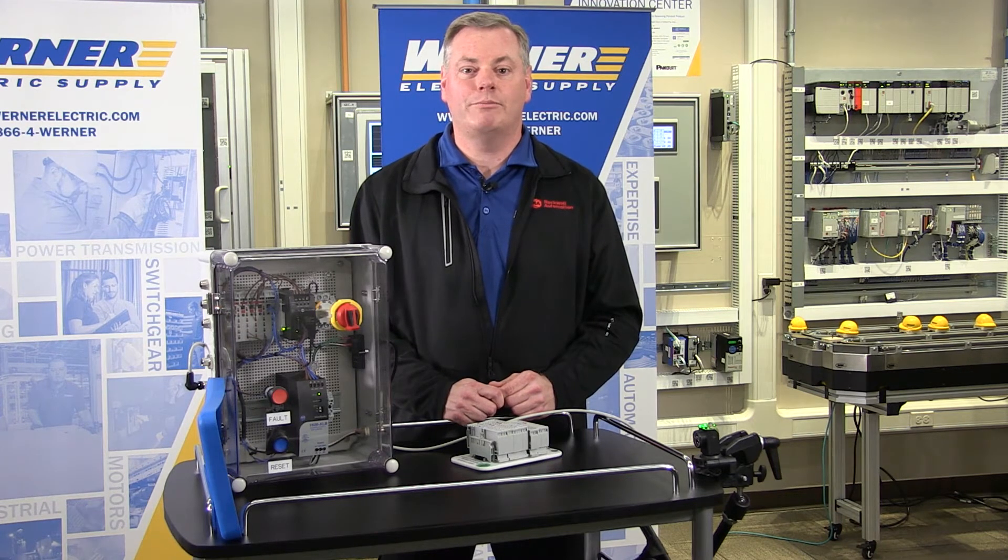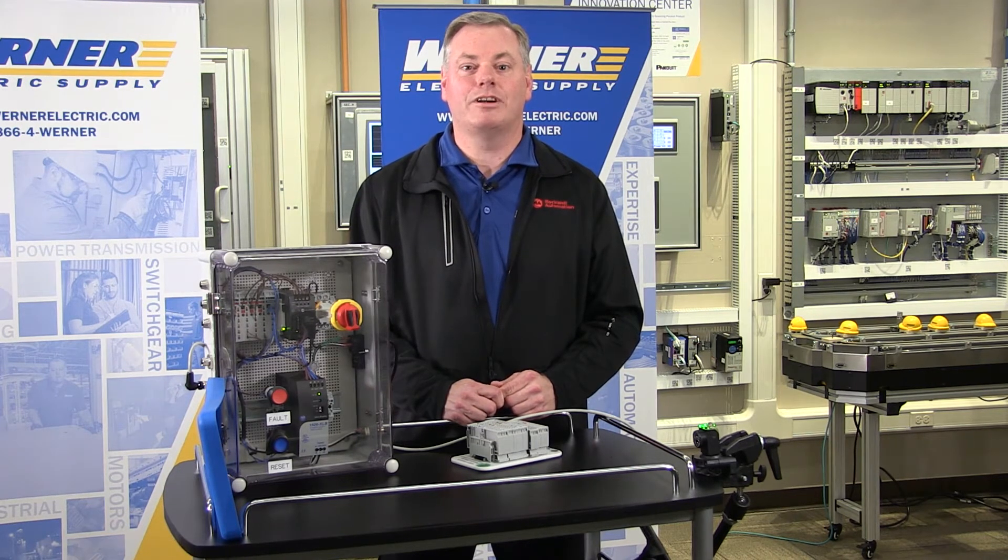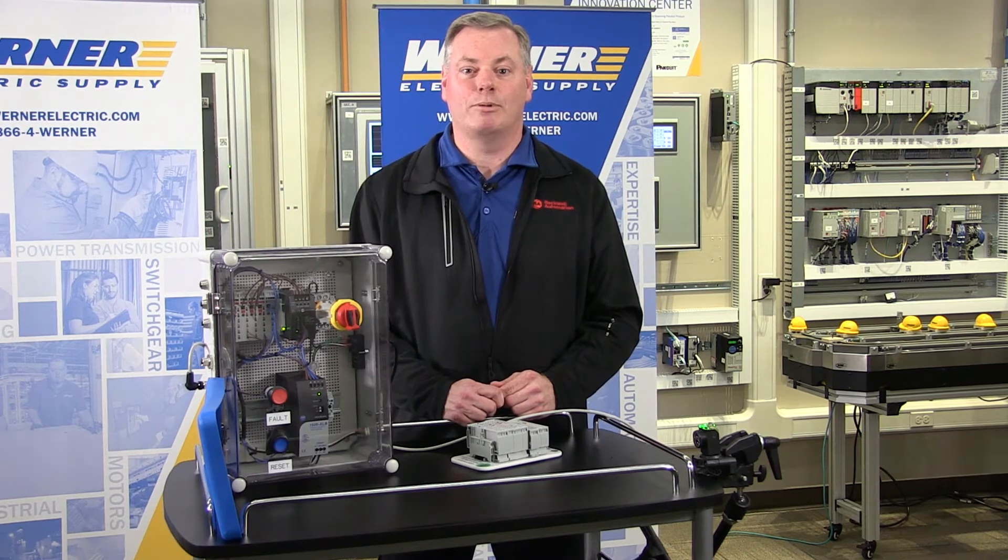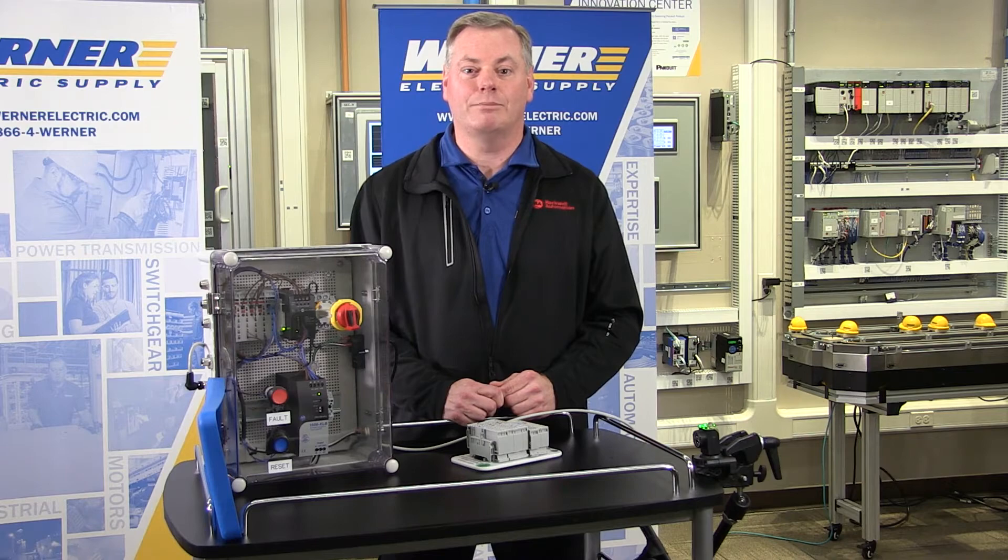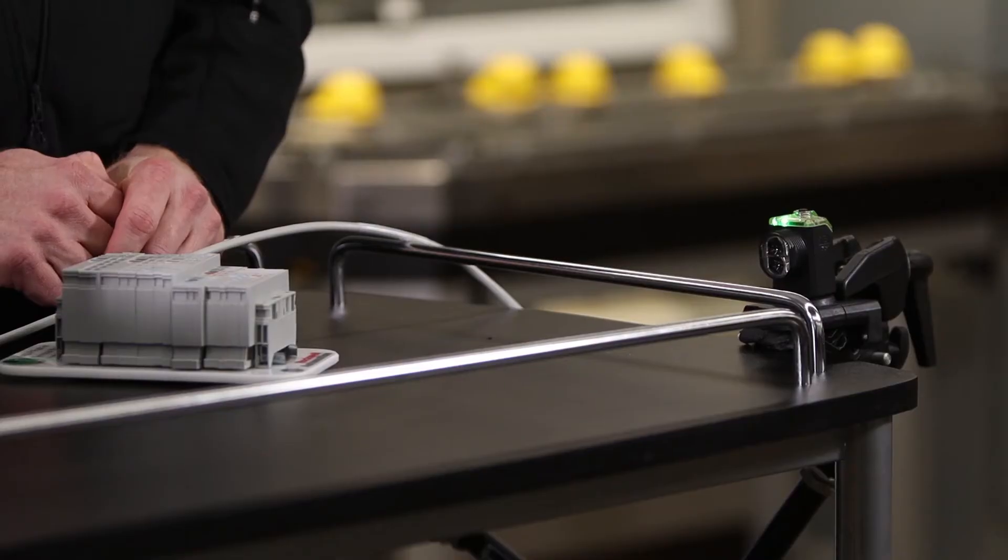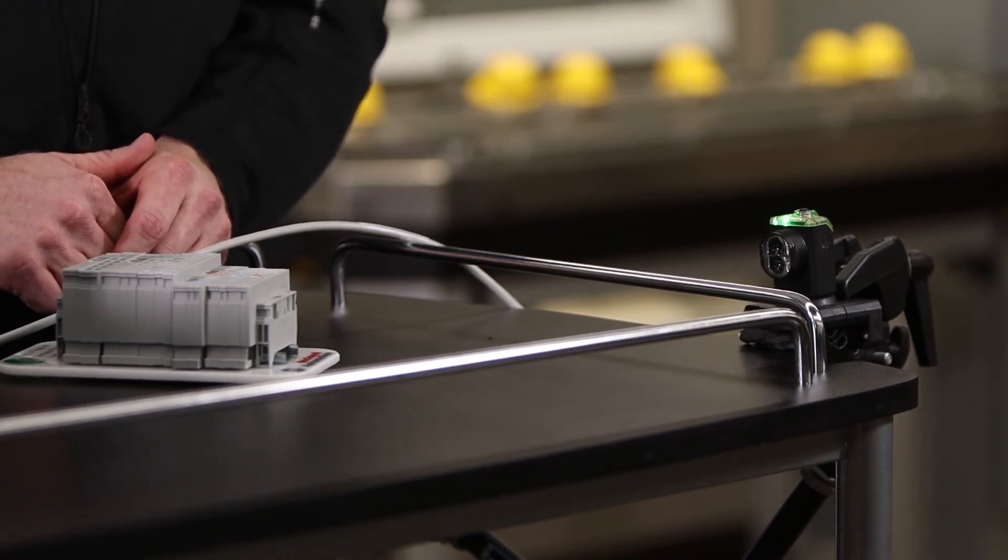The 42AF background reflection sensor also allows you to teach the sensor to function in light operate or dark operate. In case you're not familiar with these terms, light operate means that the sensor will turn on its output when the light is reflected back to it and dark operate means that the sensor will turn on its output when no light is reflected back to it. Your application will determine which is correct.